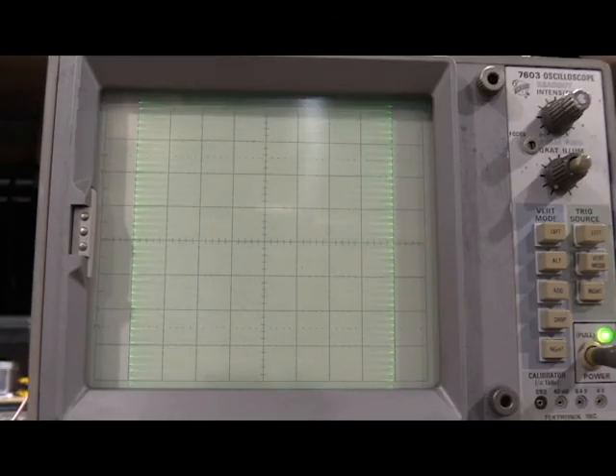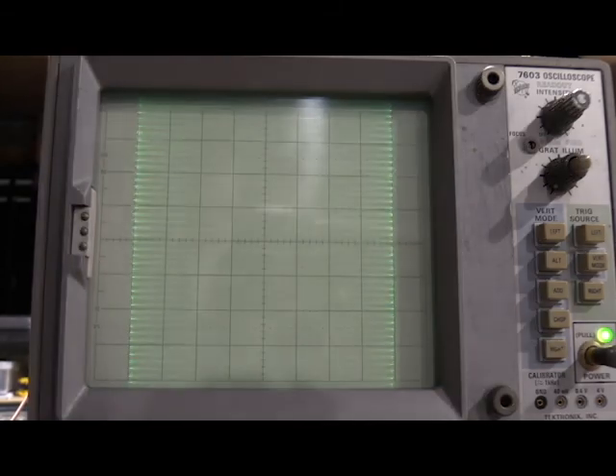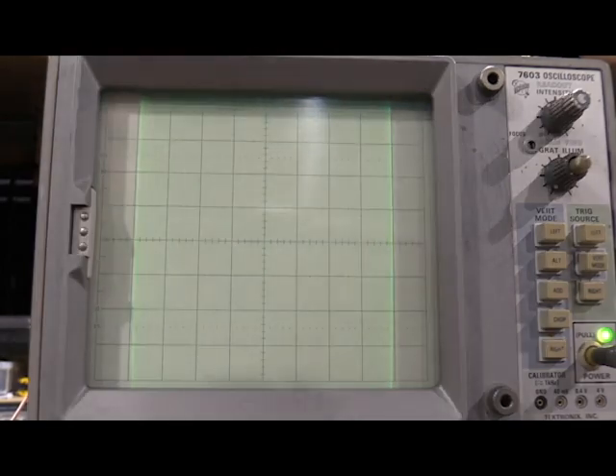Okay, I have 8 divisions of 50 kilohertz going into the scope, checking the horizontal bandwidth. So what I'm going to do is wind the frequency generator up from 50 kilohertz to 2 megahertz. It's at 50 kilohertz right now, and we should get 5.6 divisions of display. If we do, the horizontal bandwidth passes. That's 2 megahertz. Still have pretty much 8 divisions worth of display, so this scope has lots of horizontal bandwidth. So we're good there. Next section of the service manual is the Z-axis calibration.